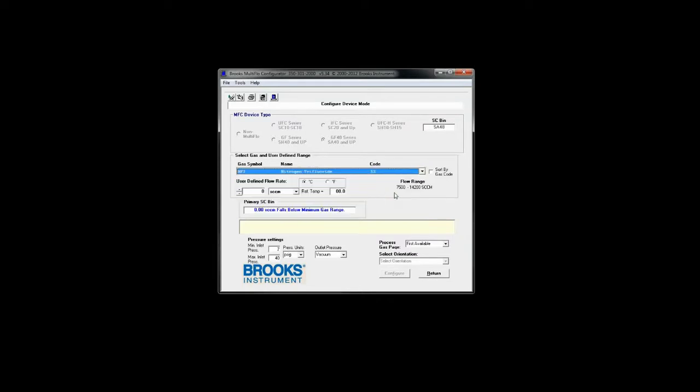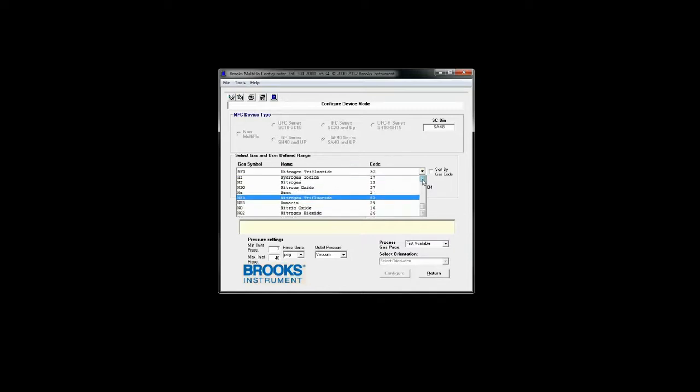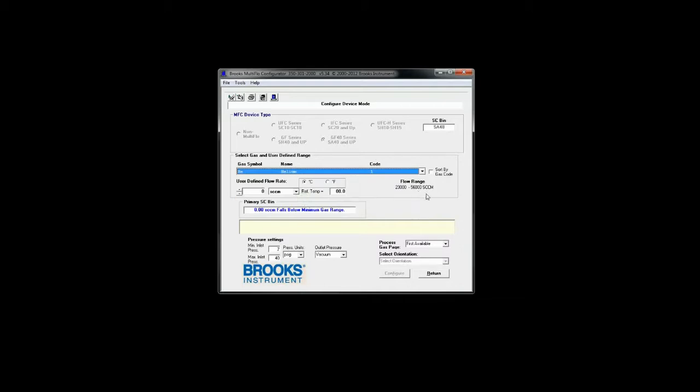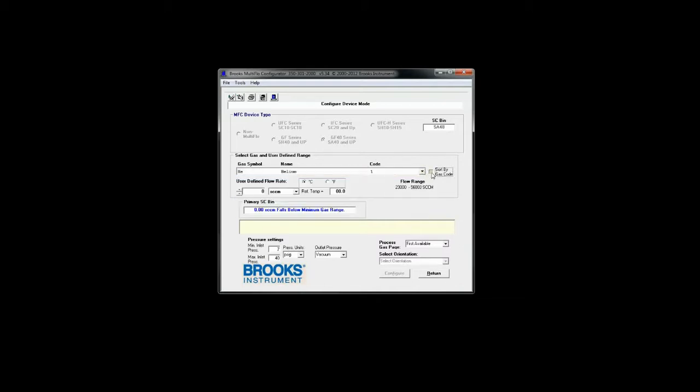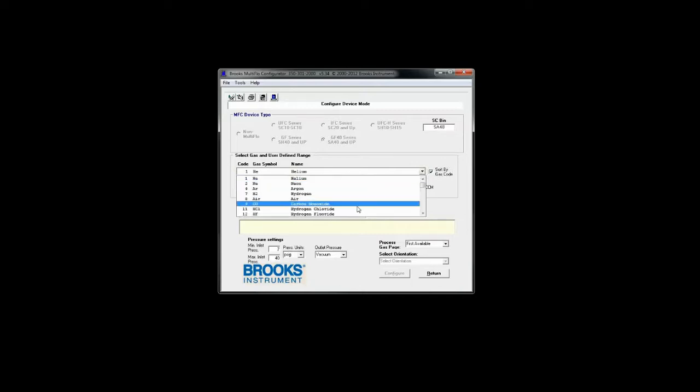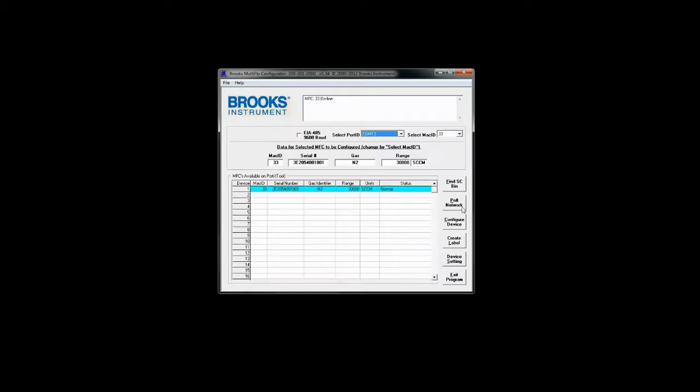If I were to change that device to be sized for something say like nitrogen trifluoride that range would change. Or if I were to change it to helium that range would change again. You can also sort the gases by semi-gas code to more easily find what you're looking for.